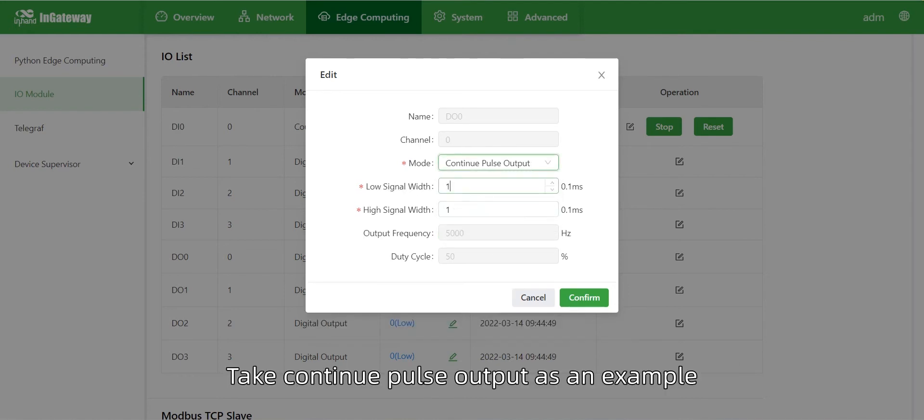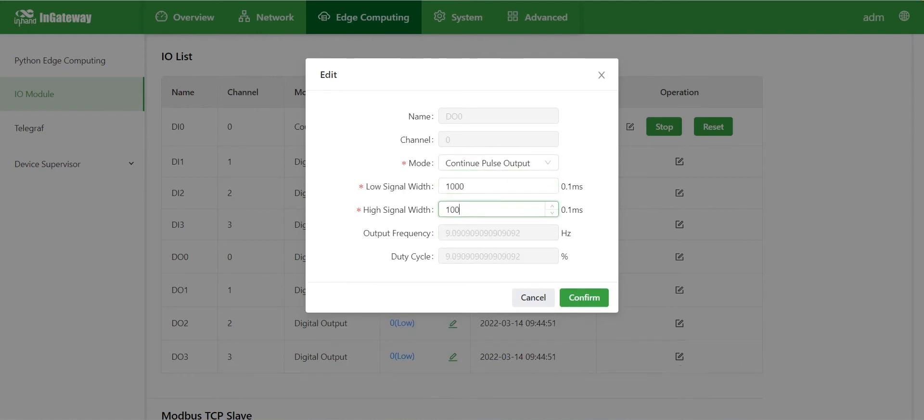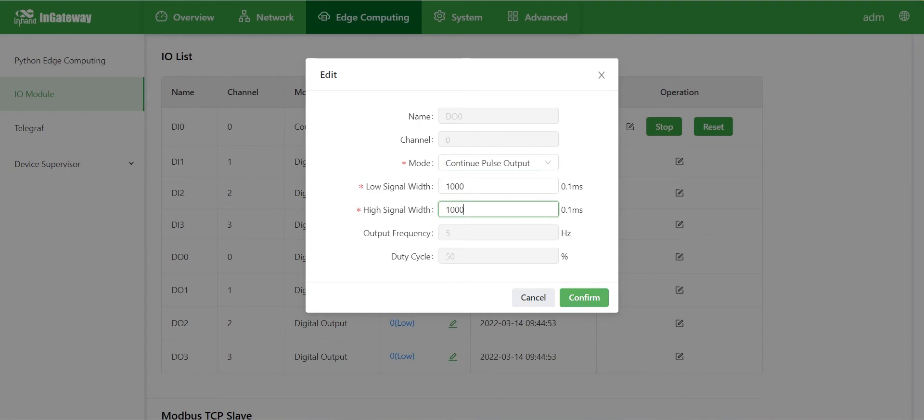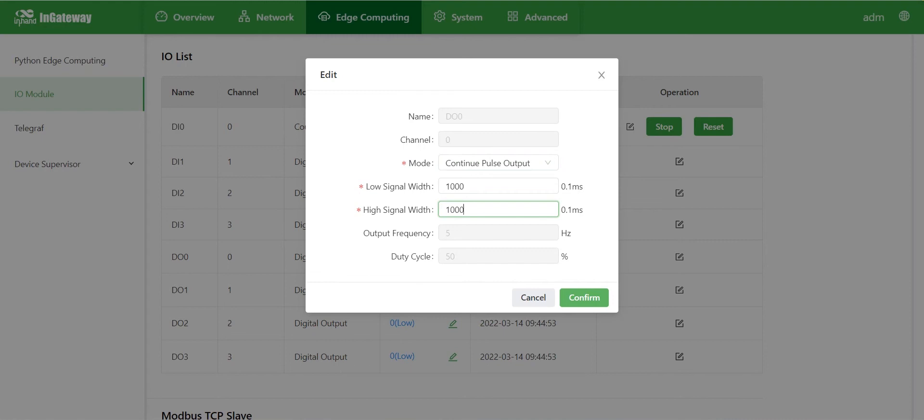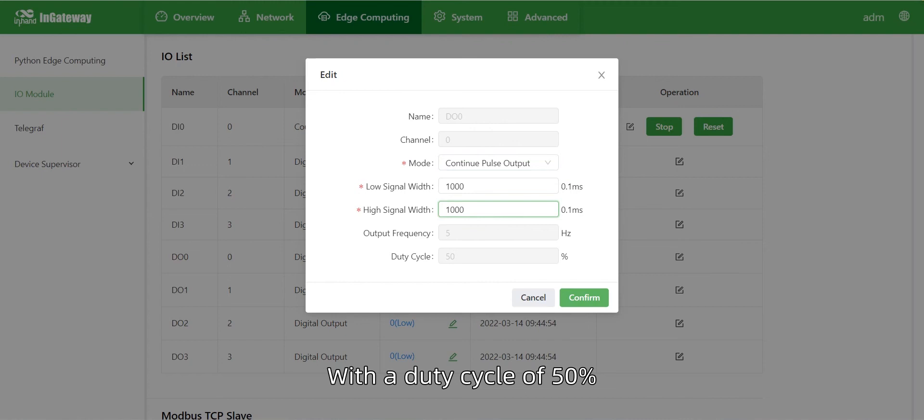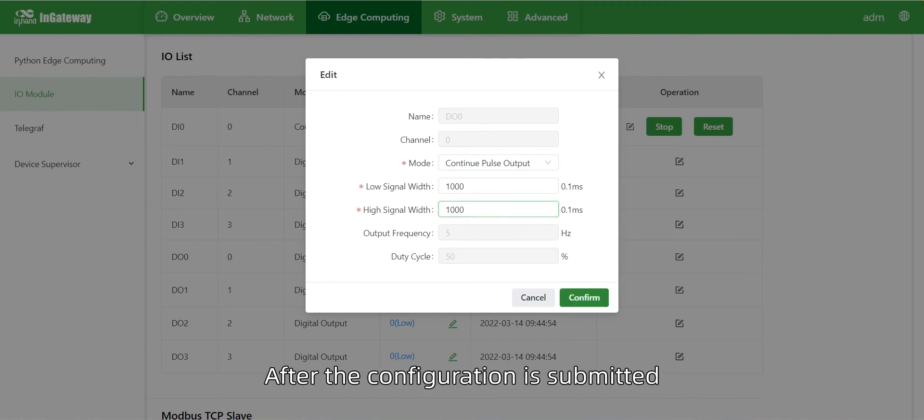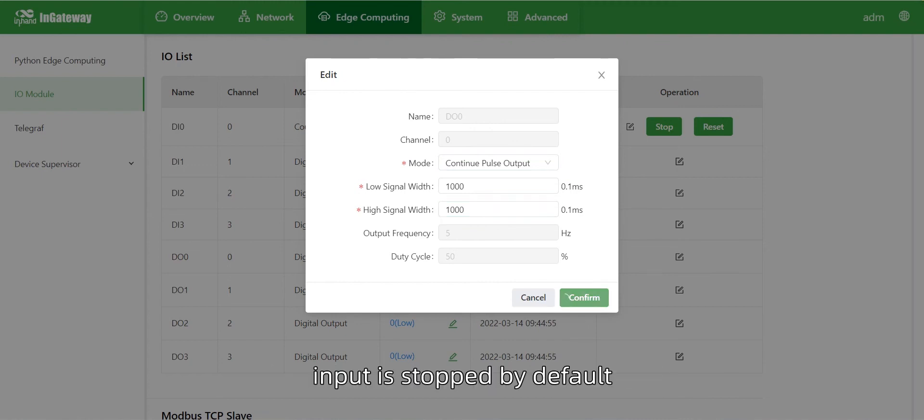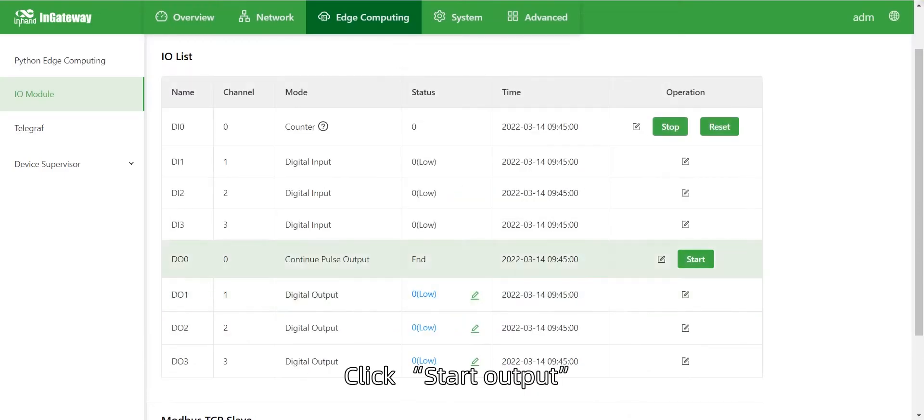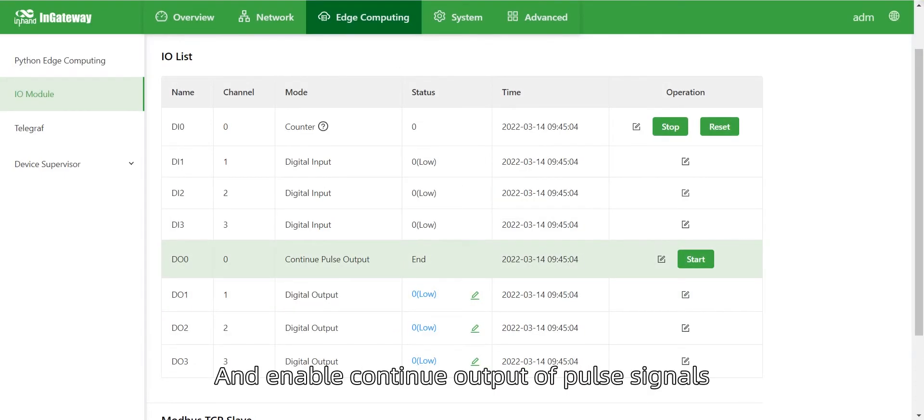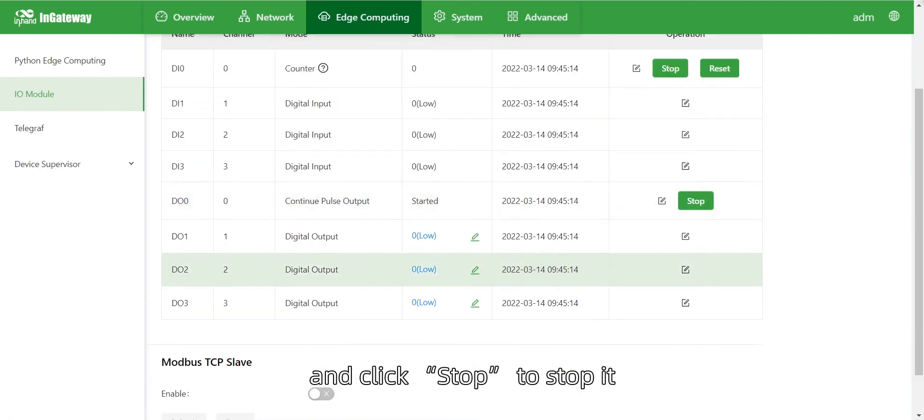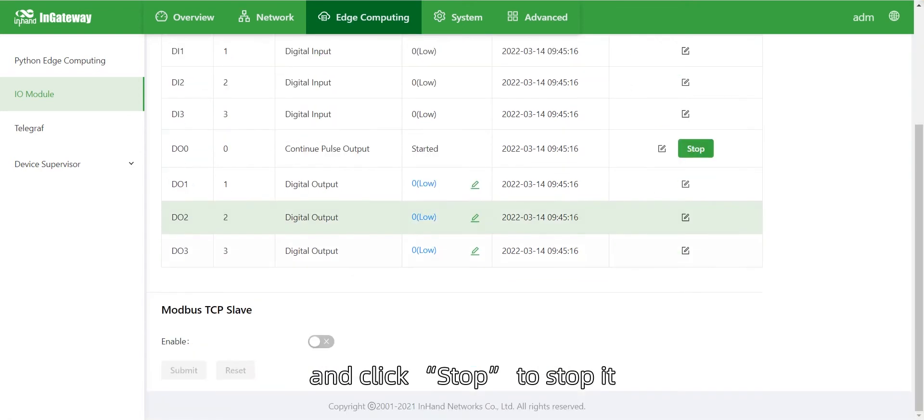Take continuous pulse output as an example. We set low and high signal widths at 1000 respectively, which is 100 milliseconds for each. Therefore, the output frequency is 5 Hz with a duty cycle of 50%. After the configuration is submitted, output is stopped by default. Click Start to enable continuous output of pulse signals, and click Stop to stop it.